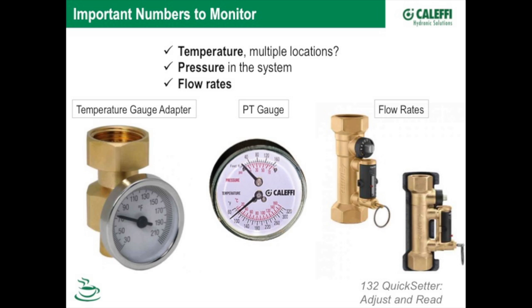Other important numbers that we wanted to monitor, I kind of showed you the pressure gauge earlier. We do have temperature gauges that are available that go on some of our devices. We offer a tailpiece that can be added on to like our mixing valves. We offer the QuickSetter Plus that has a temperature gauge. This allows us to adjust flow rates based on temperature. So if we're trying to arrive at a certain delta T or something like that, now we've got the ability to read that temperature. We do make a combination gauge, pressure and sometimes called a PT for pressure and temperature gauge here. We offer that can read pressure and temperature.